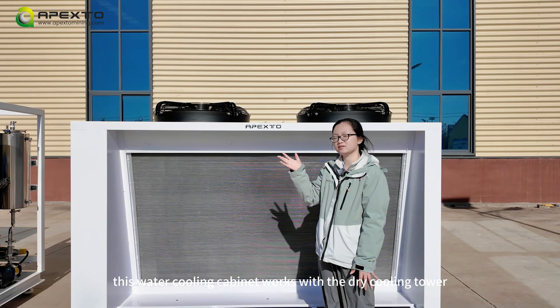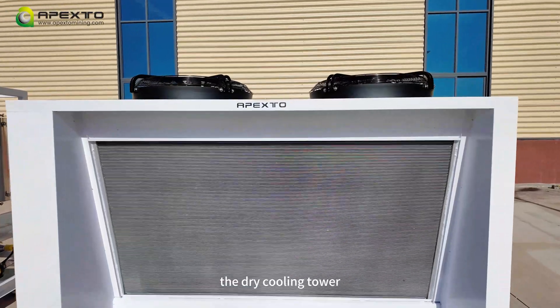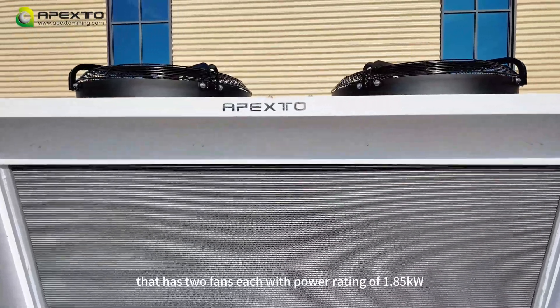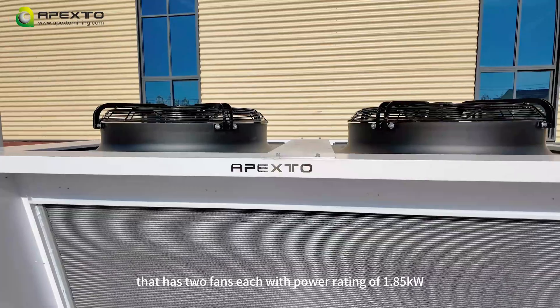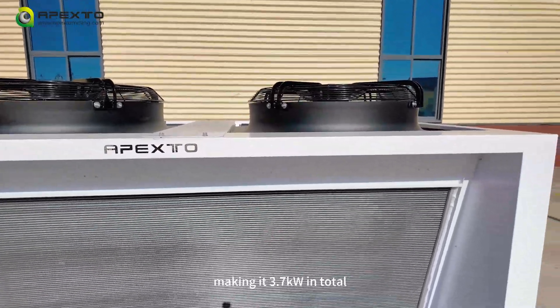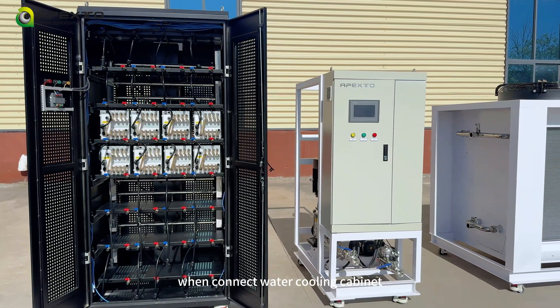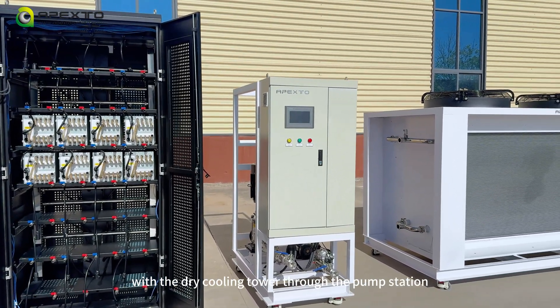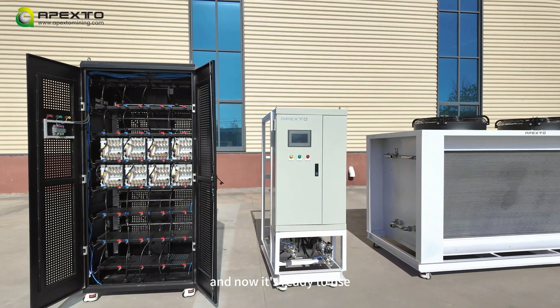This water cooling cabinet works with the dry cooling tower. The dry cooling tower has two fans, each with a power rating of 1.85 kilowatts, making it 3.7 kilowatts in total. We connect the water cooling cabinet with the dry cooling tower through the pump station, and now it's ready to use.